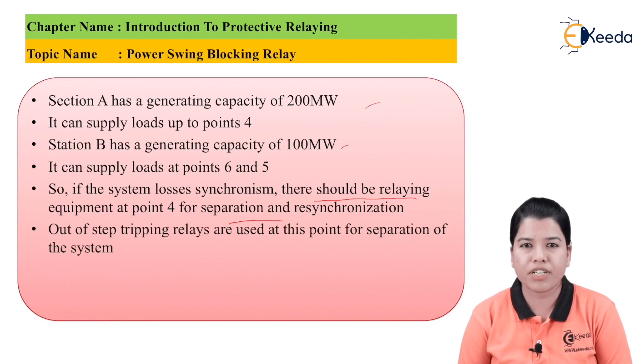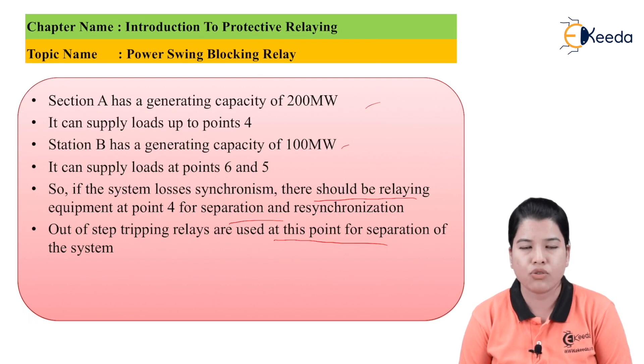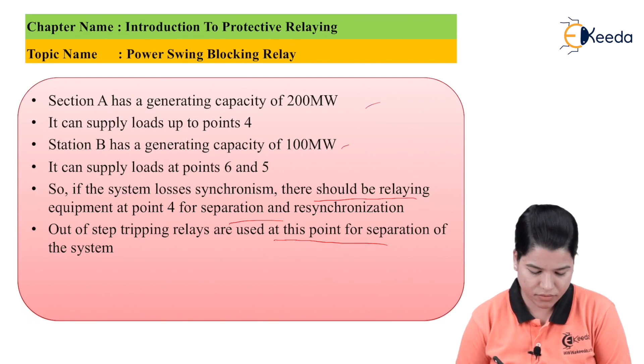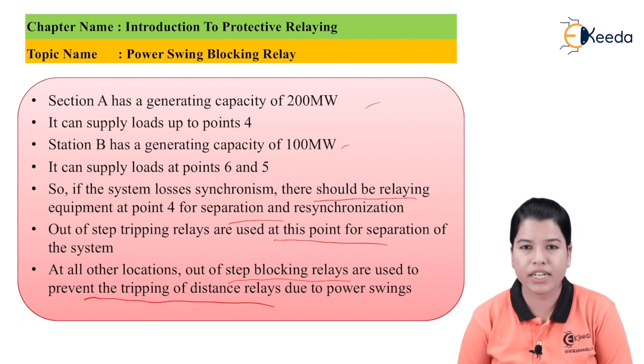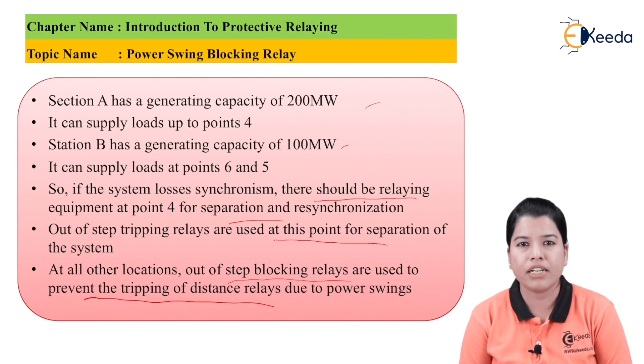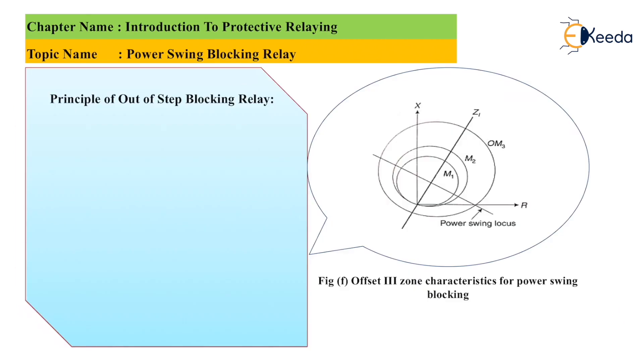Out-of-step relays are used at point 4 for separation of the system. At all other stations, out-of-step blocking relays are used to prevent tripping of the distance relay due to power swings. When the two generators lose synchronism there will be a tremendous amount of power swings, and the blocking relay prevents the distance relay from operating under this power swing condition.